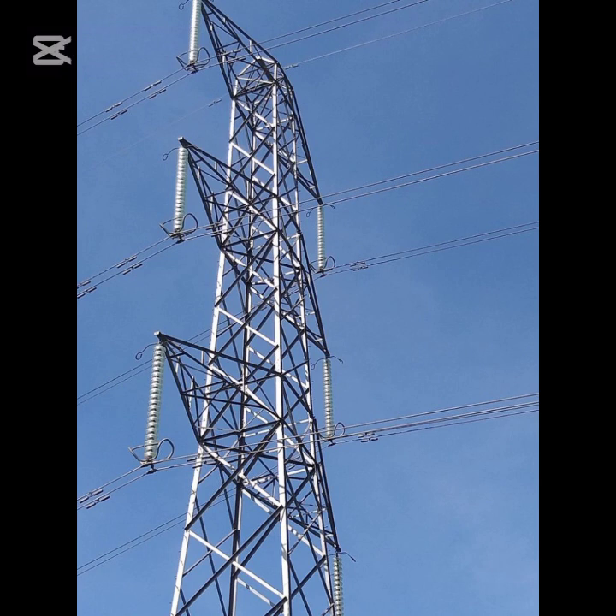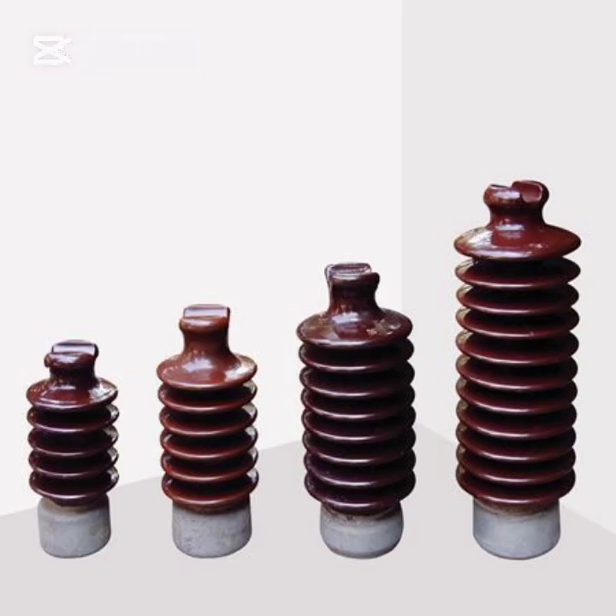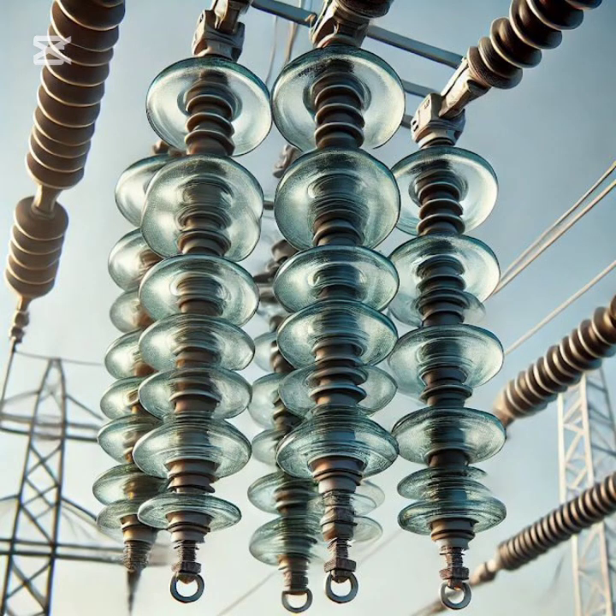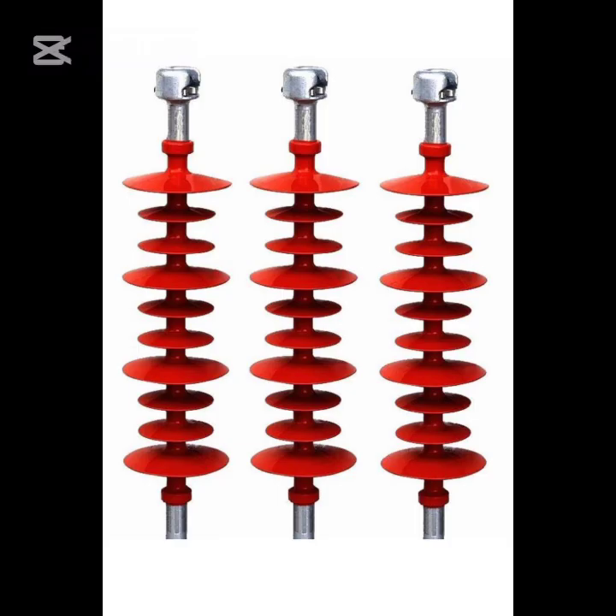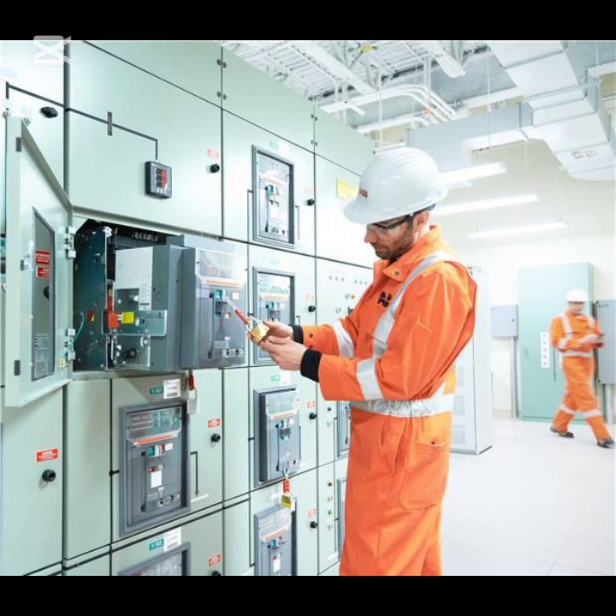Let's look at the different types of insulators. In electrical engineering, insulator types are classified in different ways: one, by voltage levels — low voltage type and high voltage type; two, by material — ceramic type, glass type, and polymer type insulators; three, by functional and configuration — pin type, suspension type, strain insulators, and shackle insulators. This third classification, function and configuration, is the best accepted way to classify insulator types, so let's dwell on it.